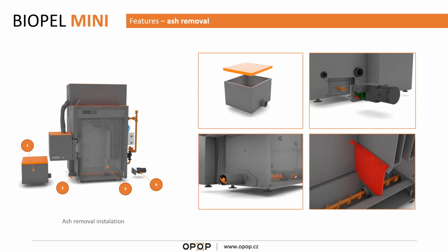And now the ash removal system, which looks like this. Basically, ash removal system is almost the same as on the V9 Premium. There is one difference. In front of the boiler there is a connection between the spiral which moves the ashes from the boiler to the ash container, and the spiral itself right now is connected, so it holds the position, because before the end of the spiral was not connected. It was basically laying on the pipe here, and because of the movement of the spiral, there have been noises coming from the ash removal system when it was in operation. So right now the spiral is connected, which means that it doesn't touch any surface inside the boiler, and there are no noises because of that.